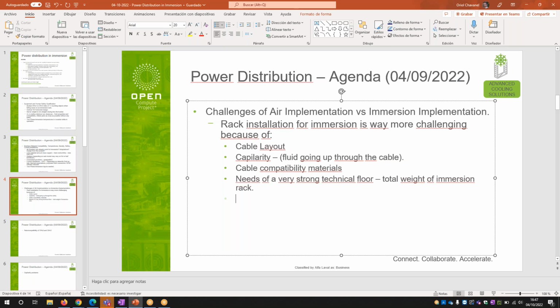We need not to exaggerate the floor loading concern with immersion. The racks now are horizontally oriented, so the footprint on the floor is considerably greater. The good news is that power capability of the rack also went up, so you end up with higher power density capability, but you're spreading that load out. Depending on the IT load, you often end up with very similar loadings per square meter between an immersion rack lying on its back versus a vertical air-cooled rack on a smaller footprint.